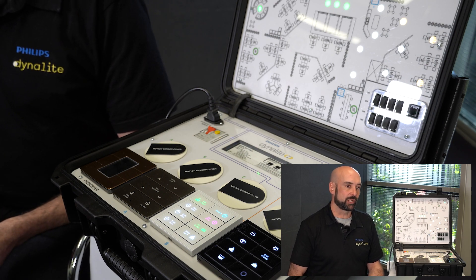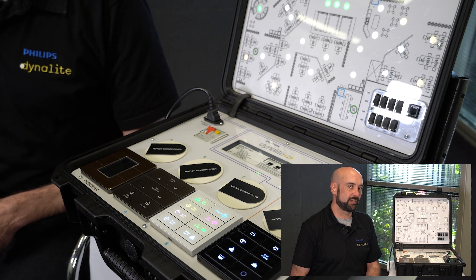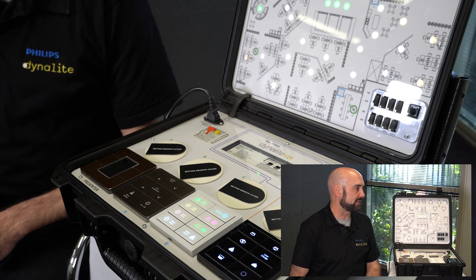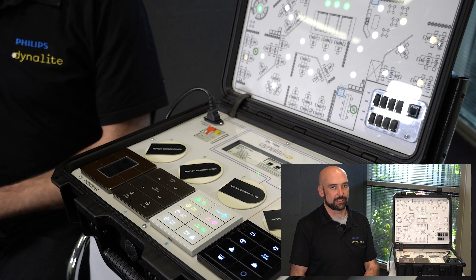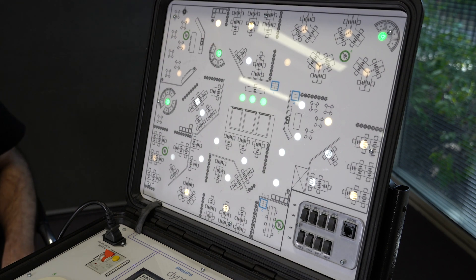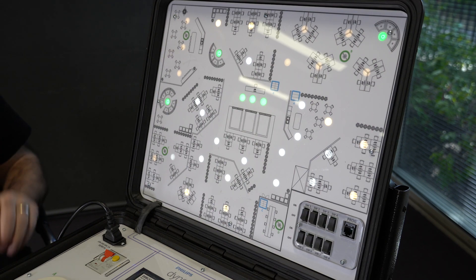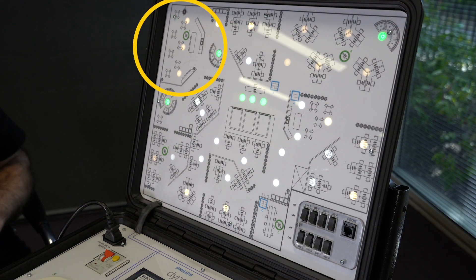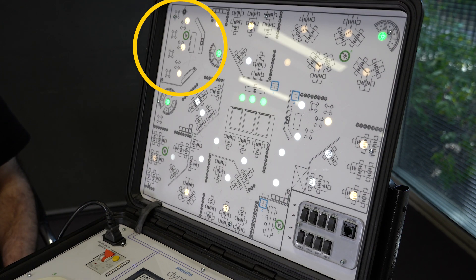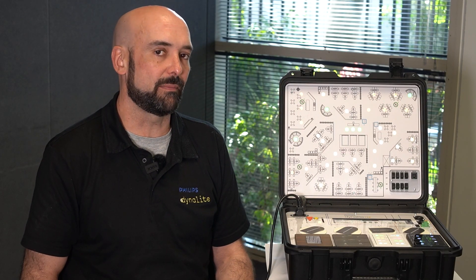For the next mode we push the system into afternoon, which changes the timeout periods and the preset table. The sensors now call preset scenes from 100% to 10%, so when an area is unoccupied the lighting is set to a very low level — as may be an occupancy requirement — and when an occupant is detected the lights drive to 100%, timing back down to 10% when unoccupied. This shows how sensors can recall different scenes depending on what we need them to do.